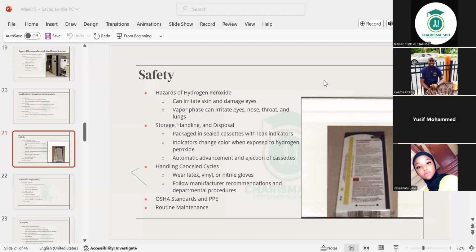All right. So the hazards of hydrogen peroxide: it can irritate skin and damage eyes. Vapor phase can irritate eyes, nose, throat, and lungs. For storage, handling, and disposal, it's packaged in sealed cassettes, as I told you, and indicators change color when exposed to hydrogen peroxide. The yellow line you see there, at times it could be a white line, is going to turn red if there's a leakage in the cassette, in that plastic container, in that sealed pack.